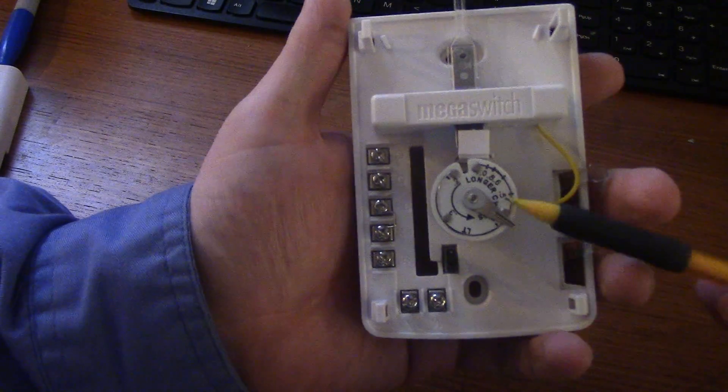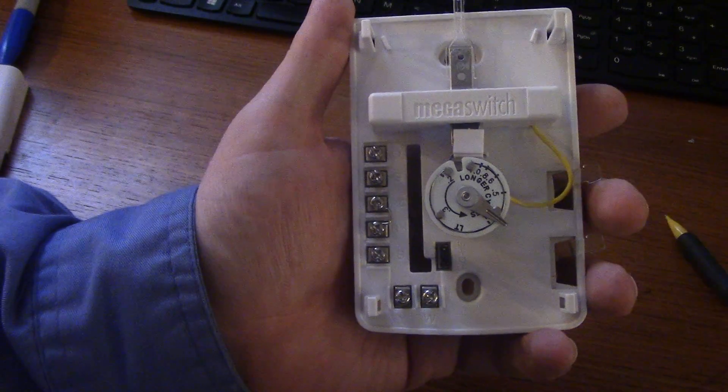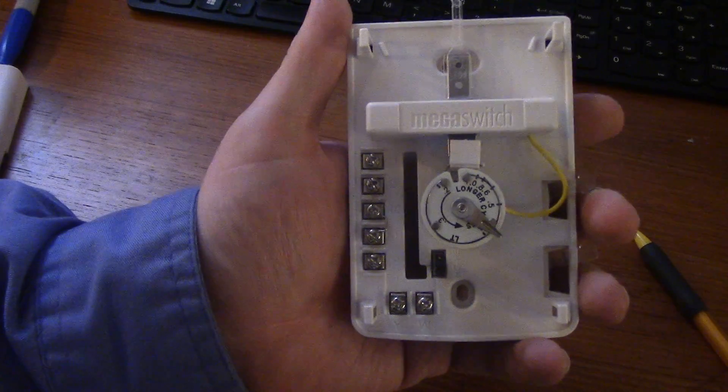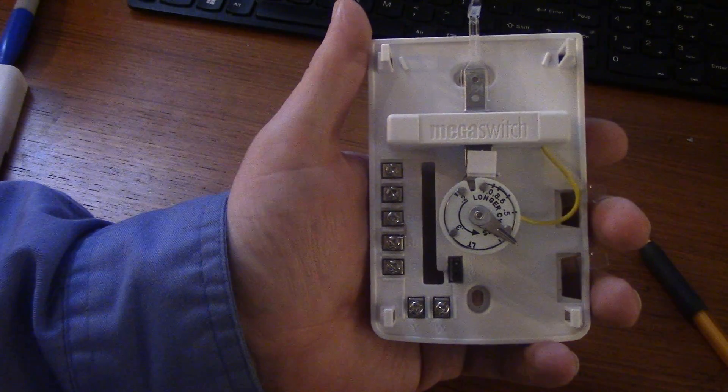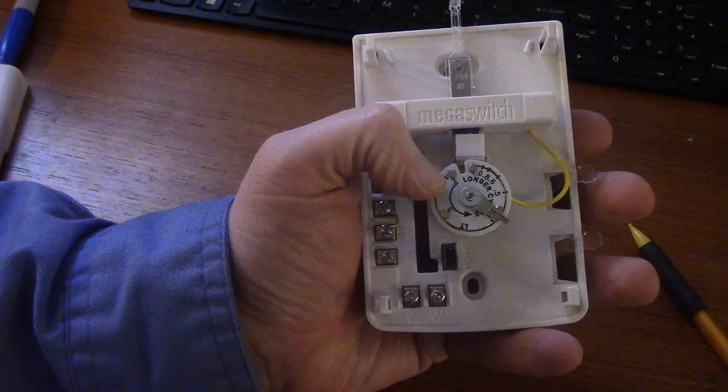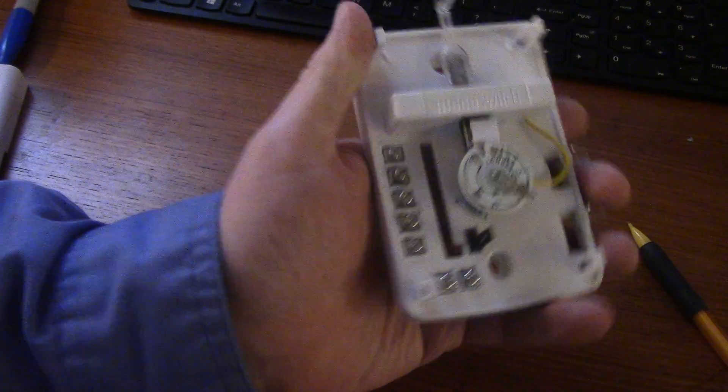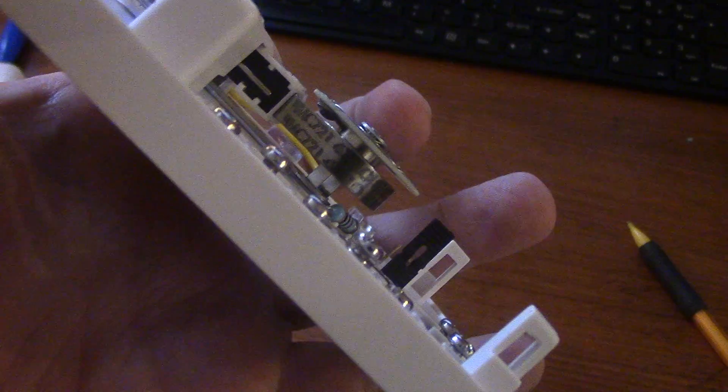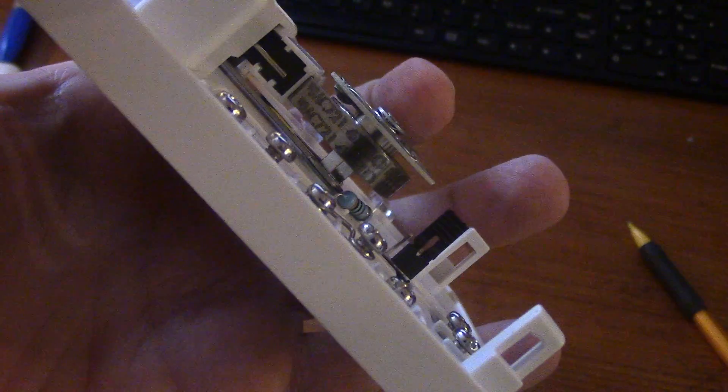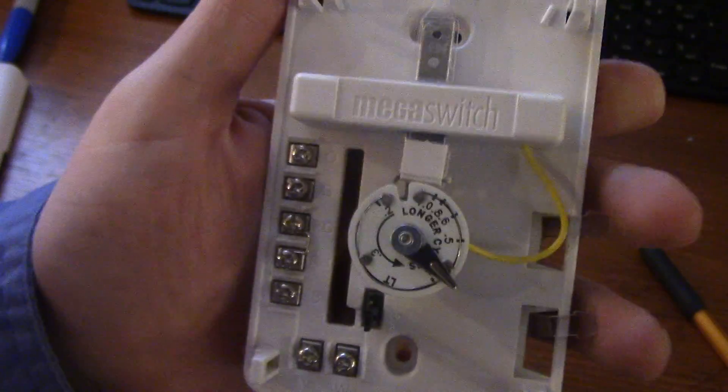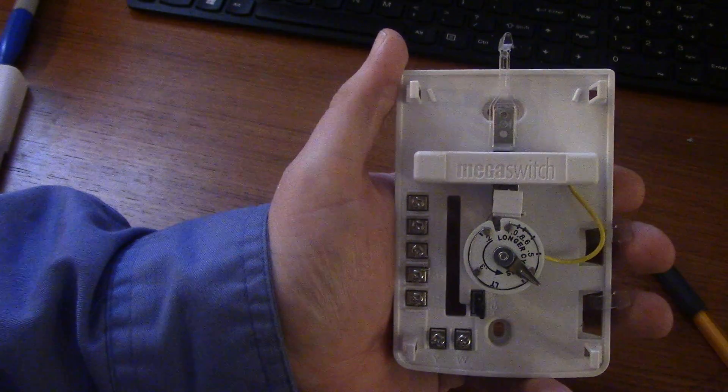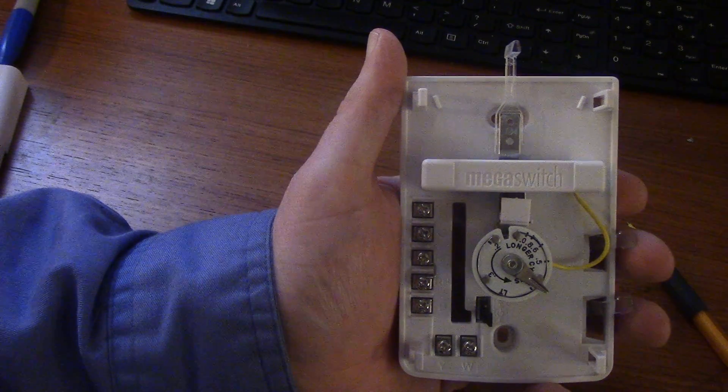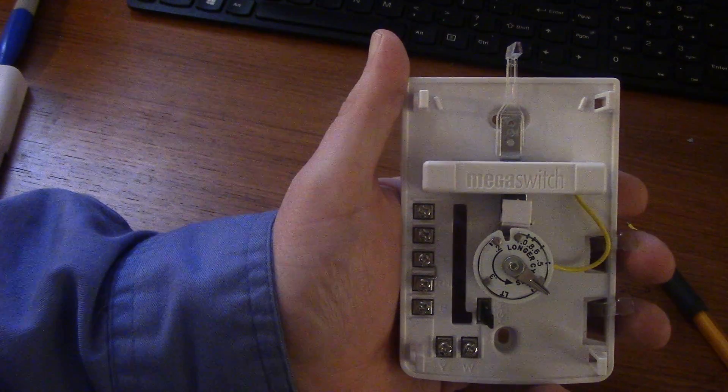Okay, this portion right here - that's called your heat anticipator. You have to set it for this to run appropriately for comfort in the home. What it does is this is a heater that will warm up to turn the bi-metal switch or bi-metal portion there, expand and open this heating circuit sooner. So when the blower continues to run, it washes the heat off the heat exchanger and you're not overheating the house. It's called the heat anticipator - it anticipates the heat.